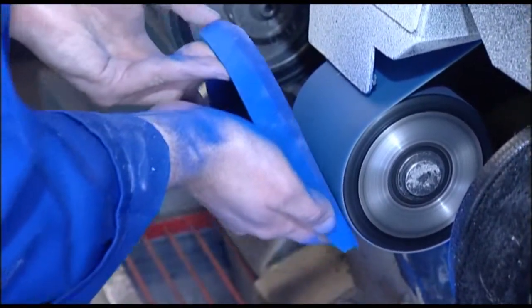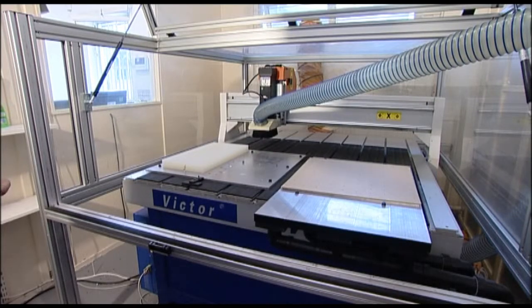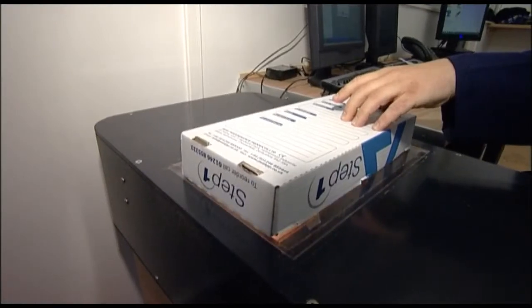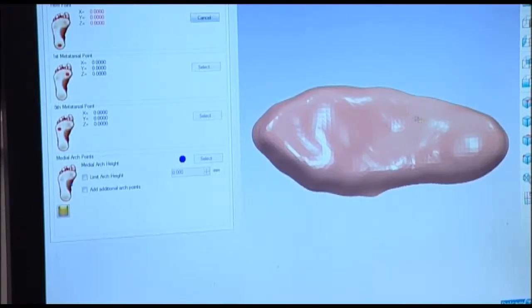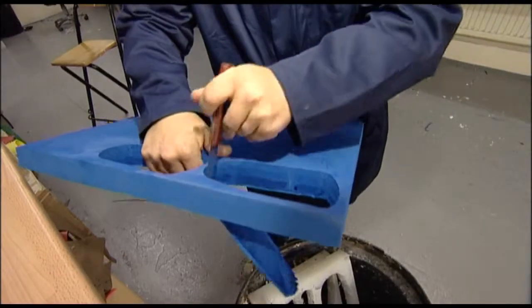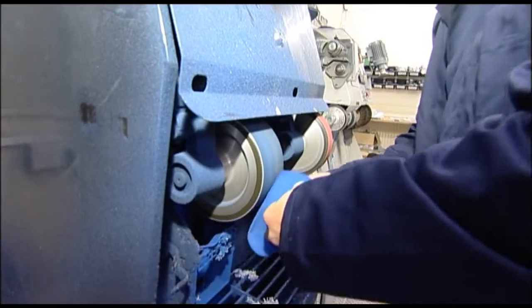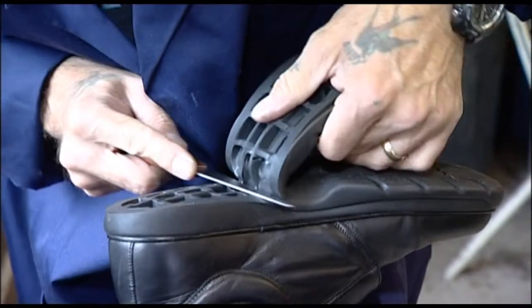To a template, any modifications needed — top covers, posts — and then tracked out. CAD/CAM is a newer process: rather than filling the impression box with plaster, it's scanned onto the computer where the software makes a model with all the relevant rectifications. The information is then saved and sent to the CNC machine, which cuts it out rather than vacuum forming. When it comes off the machine, it's ready for trimming, fitting to an insole, and any modifications needed. The advantage of CAD/CAM is the repeatability — because it's saved in the software, if it fits the first time, future repeats should be exactly the same.